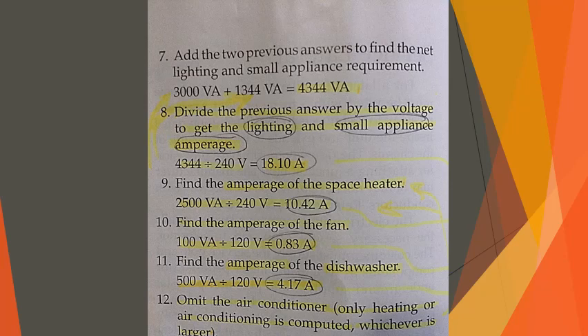Step 12, omit the air conditioner. Only heating or air conditioning is computed, whichever is larger. In this case, step 13, find the amperage for the range, which is 8000 VAs divided by 240 volts, which is 33.3 amps. Step 14, reduce by 80%. So 33 amps times 0.8, or 80%, is 26.64 amps. Step 15, find the amperage of the water heater, which in this case is 5000 VAs divided by 240 volts, or 20.83 amps.